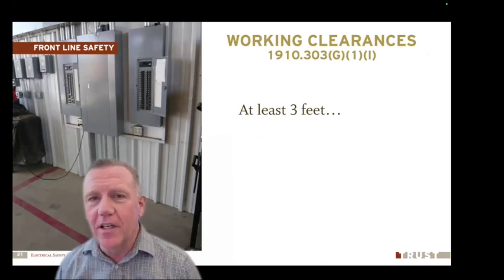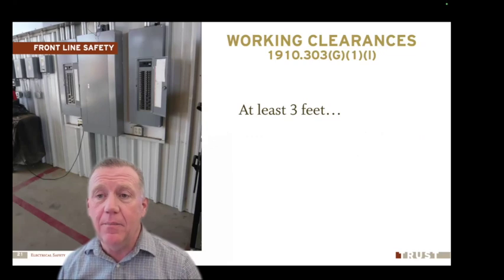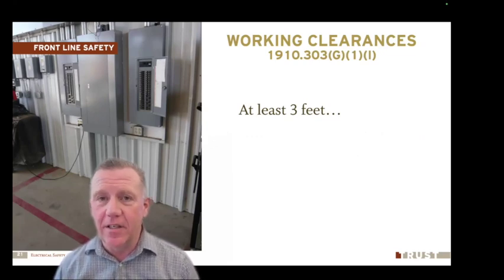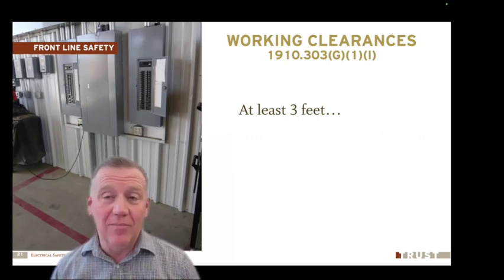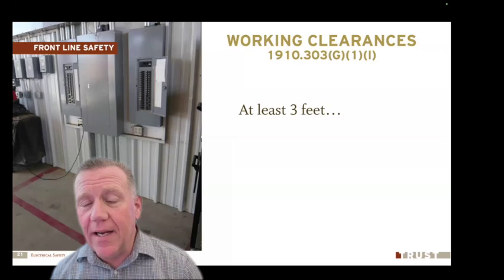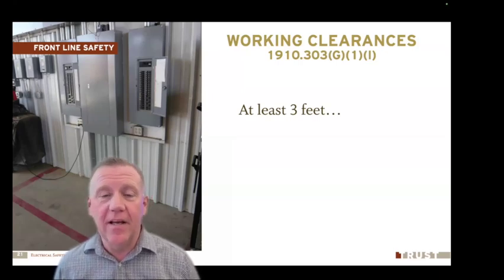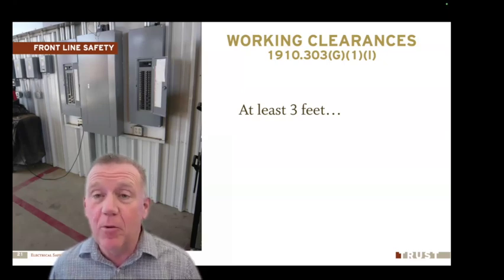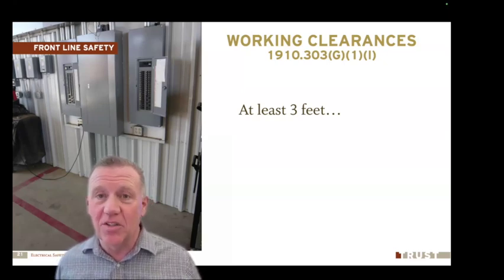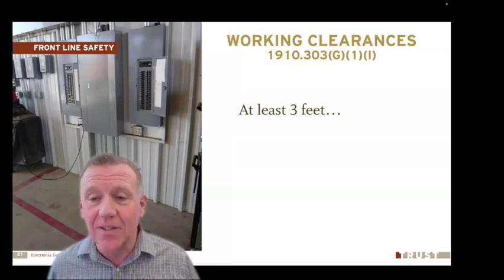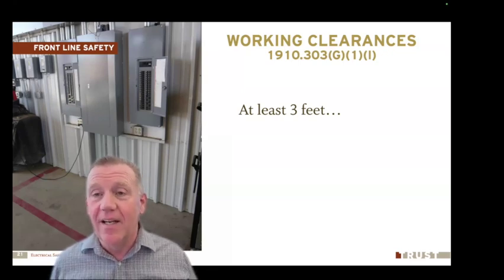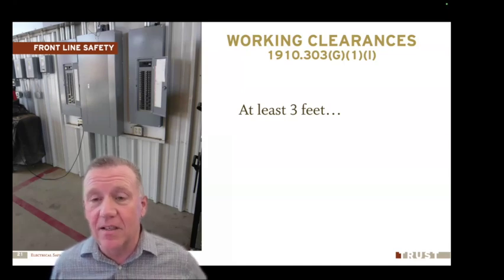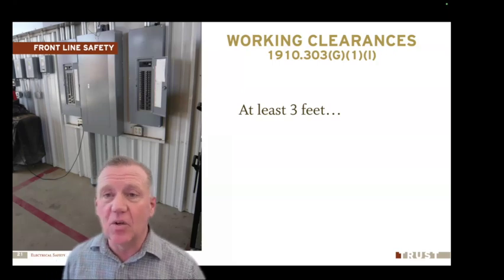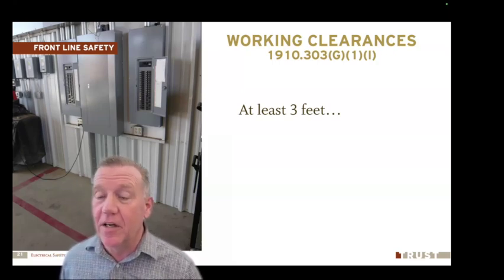We need to have effective working clearances for our electrical equipment. So if I've got an electrical panel, it needs to be clear of obstructions - from the floor up to 7 feet above, and at least 3 feet wide. I need a clear opening; I can't put a cart or garbage can in front of it. That's for a number of reasons: I need to be able to access it in an emergency, like turning off a breaker. Also, sometimes these panels fail and shoot out sparks or get really hot, and if there's combustible material stored around them that could start a fire and we could lose the building. So keep those areas accessible - you can see in this picture it's beyond 3 feet because there are multiple panels.